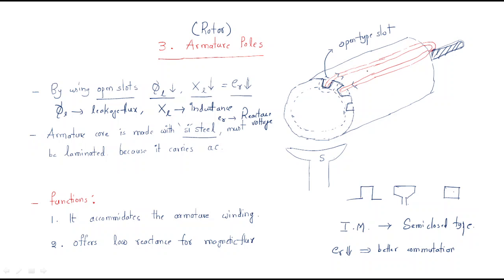The armature core is made with silicon steel and must be laminated. The silicon steel must consist of laminations because it carries AC quantities. The most important thing is that although it is in a DC machine, it produces AC quantities — that is why laminations are required. In the case of field pole cores, there are no laminations, but the armature core has laminations because it carries AC.